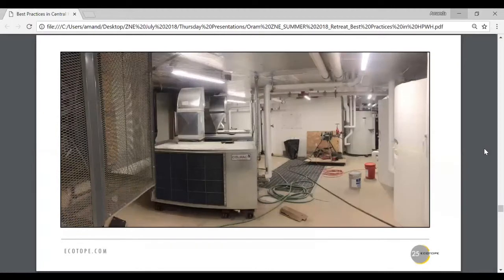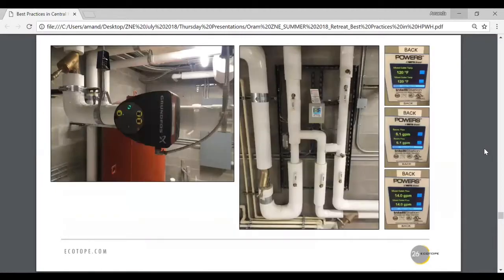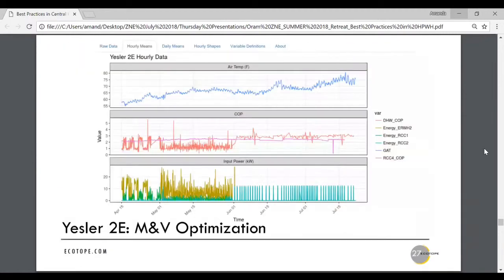Here's another angle, showing some more space. I realize I have 1 minute. In our designs, we've got dedicated heat pumps for primary water heating and dedicated ones for the ring main, or what we call temperature maintenance. We bring them together into a motorized, automated mixing valve by Powers—it's a great valve to use, it can take any variation and deliver your output water.